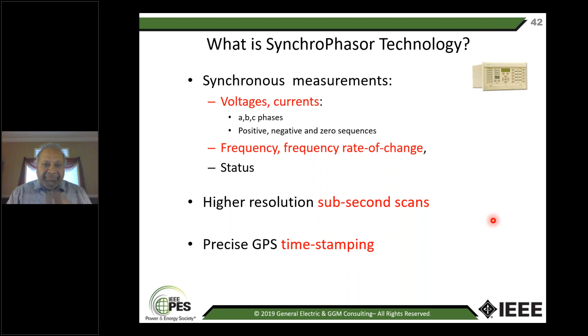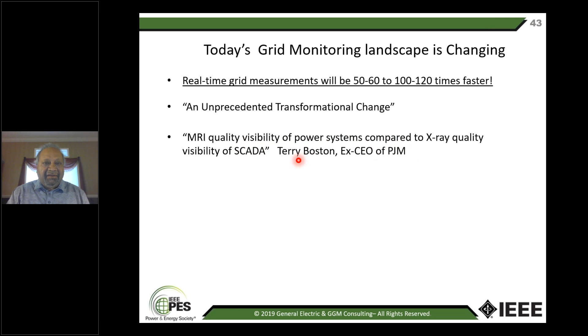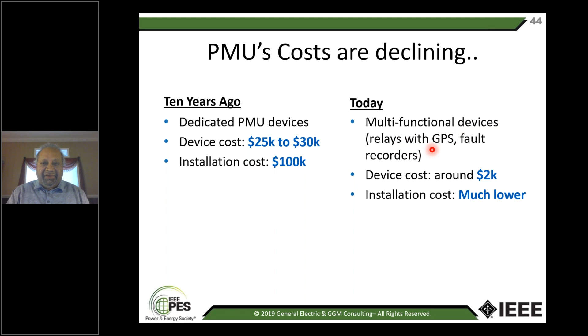It's an unprecedented transformational change. And Mr. Terry Boston, who used to be CEO of PJM, really pushed a lot of the PMU technology at TVA and PJM. And he compares PMUs to MRI versus the X-ray visibility of SCADA. The costs are declining. They used to be more expensive. Installation was more expensive because you needed high-speed communication, but now a lot of the substations have high-speed communication, and the device costs are much less expensive. And we also have other multifunctional devices like relays with GPS and fault recorders, which provide similar information.